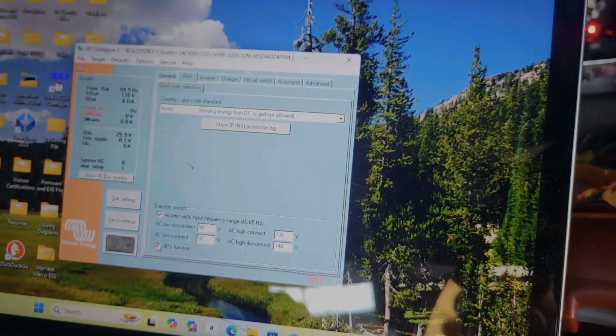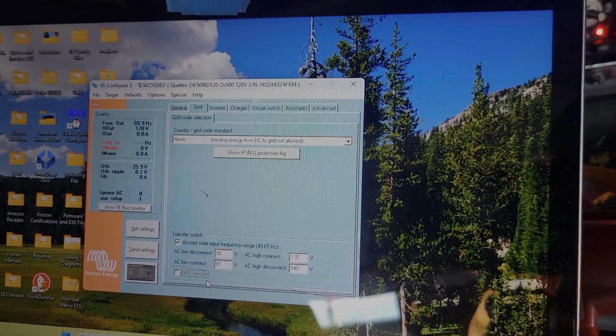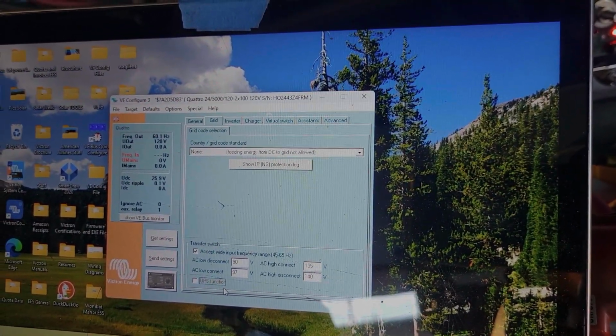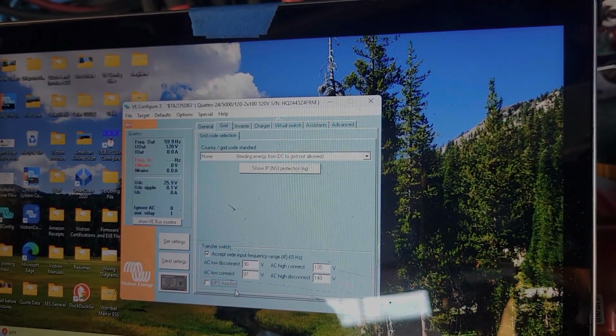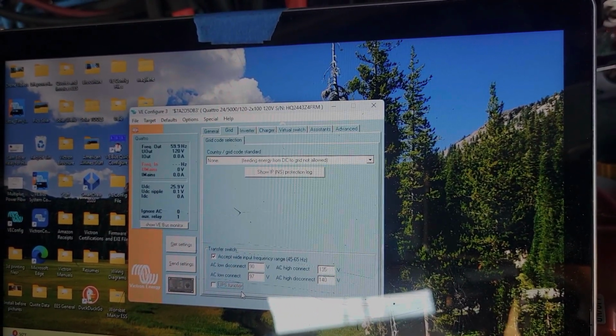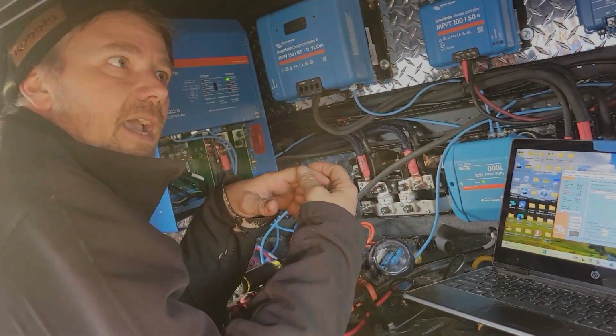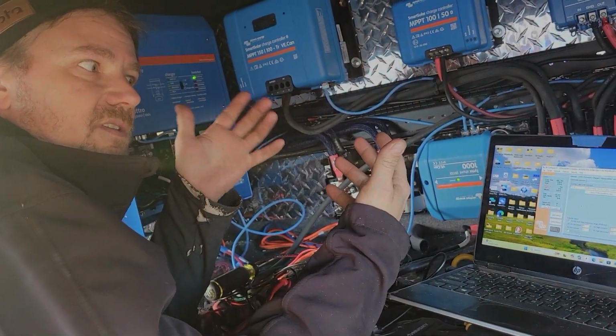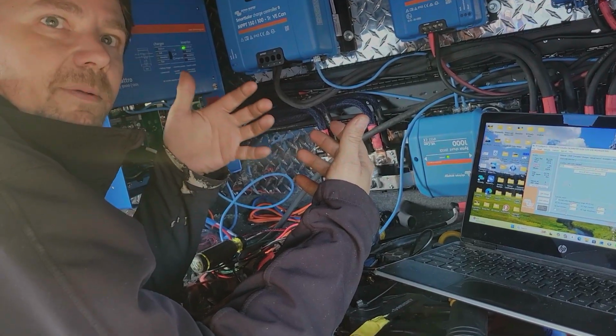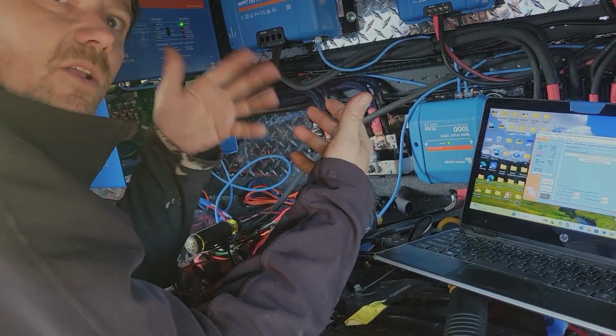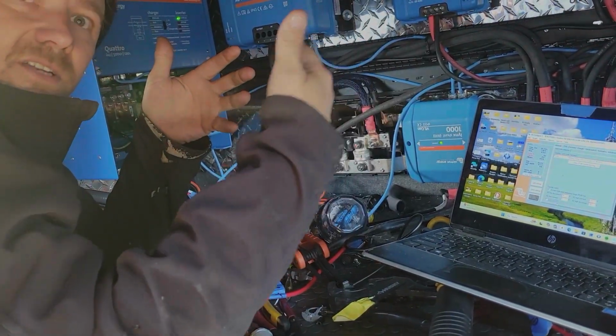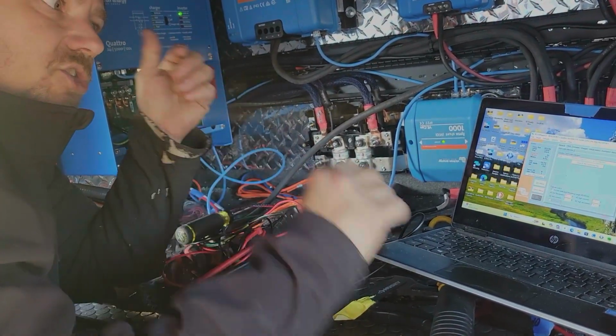If I want the charger to activate on an Onan generator, I would disable that, because the UPS function is trying to closely match the inverter sine wave with what's coming in. Right. Okay? And you don't want it bouncing all over the place. If I'm trying to match the sine wave with a really crappy generator whose sine wave is all over the place, the inverters won't sync. They're going to be all over the place and they would never mesh.